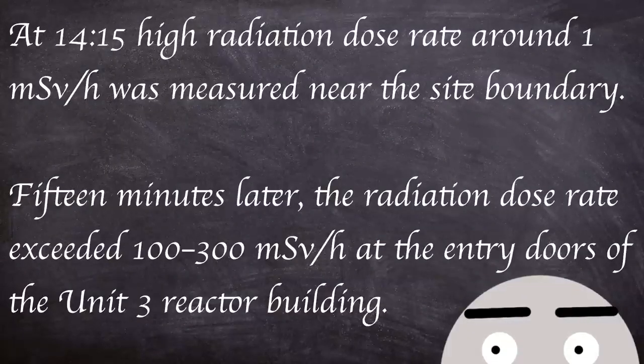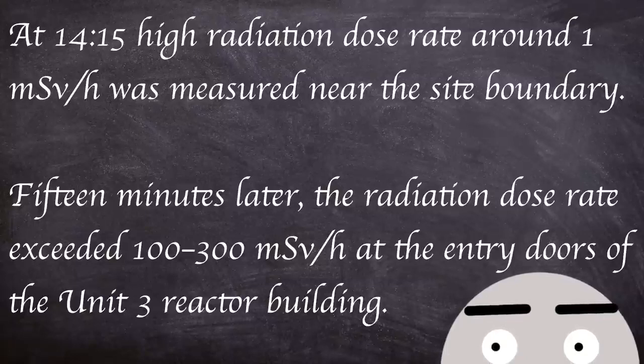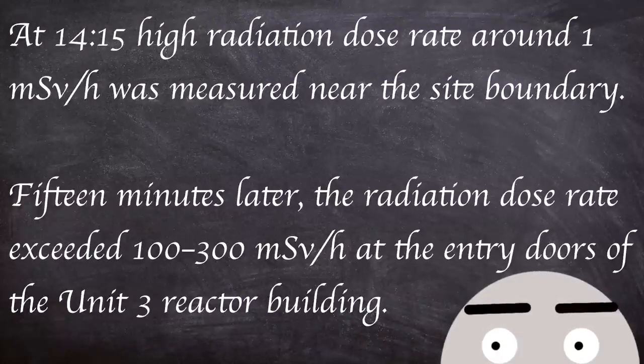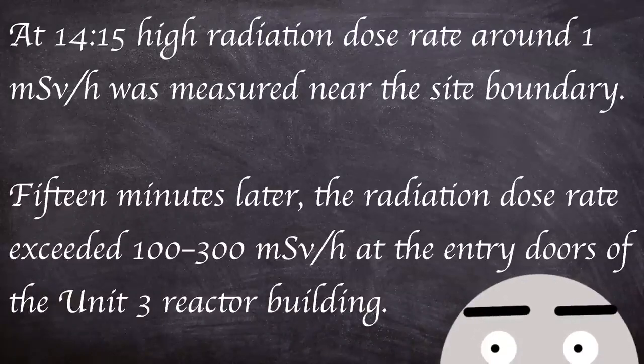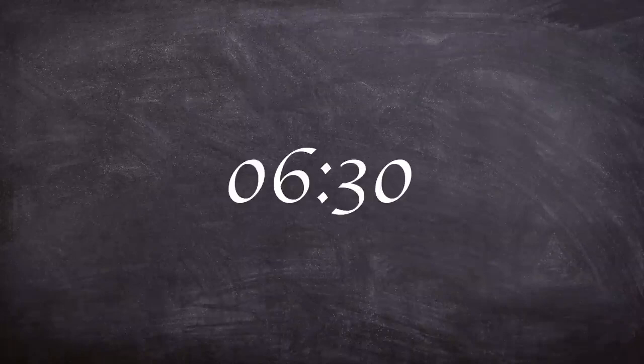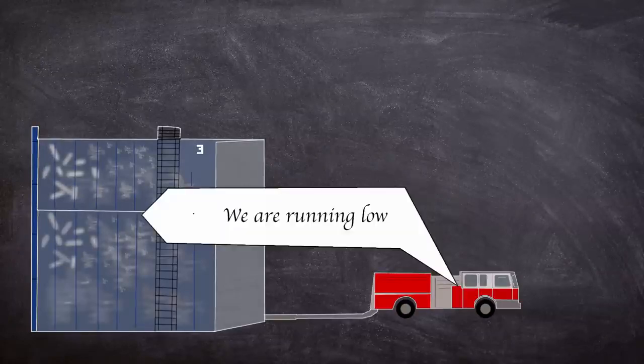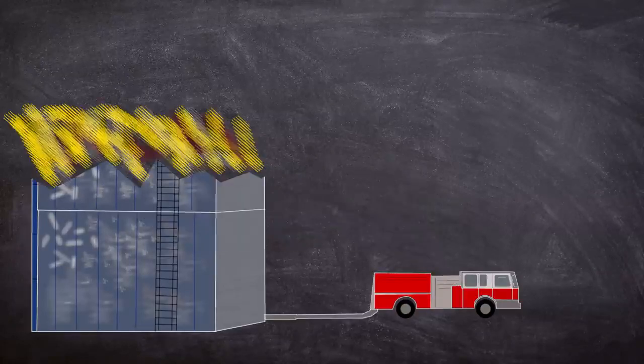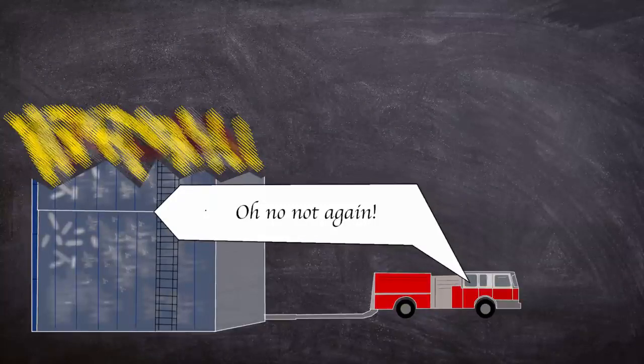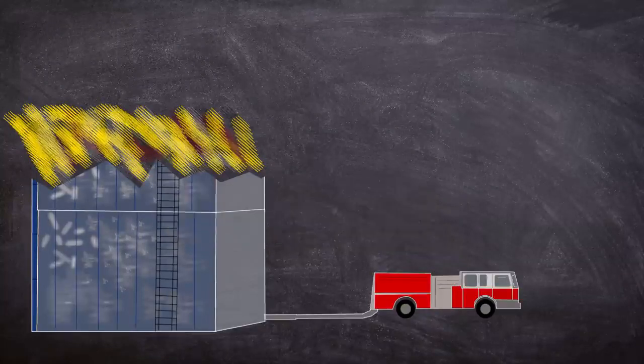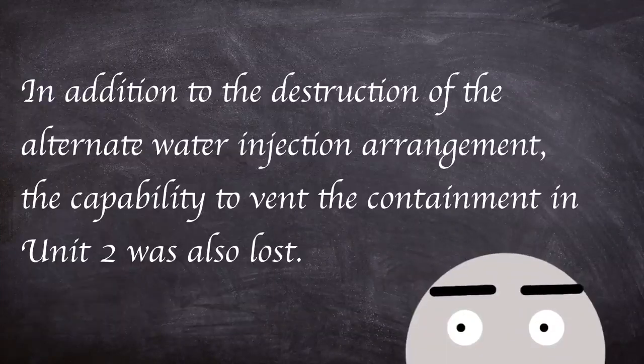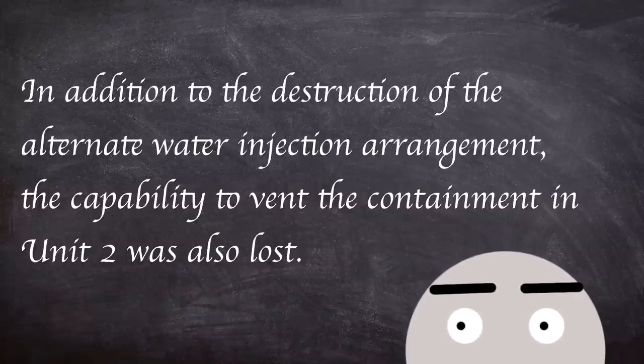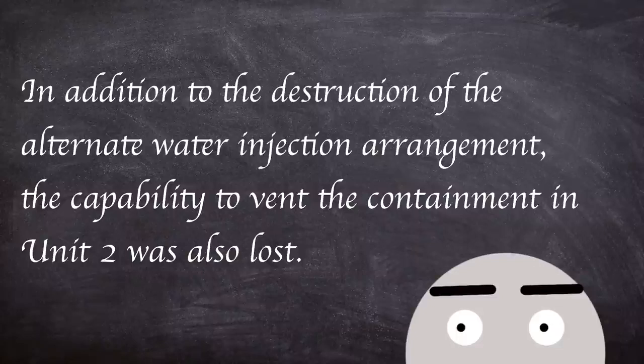At 2:15pm, high radiation dose rate of around 1 millisievert an hour was measured near the site boundary. 15 minutes later, the radiation dose rate exceeded 100 to 300 millisieverts an hour at the entry doors of the unit 3 reactor building. At 6:30am on the 14th, the water level in unit 3 dropped as cooling water supplies that were being pumped began to dwindle. At 11:01am an explosion occurred in the upper part of the unit 3 reactor building, similar to what happened at unit 1, destroying the structure above the service floor. In addition to the destruction of the alternate water injection arrangement, the capability to vent the containment in unit 2 was lost.